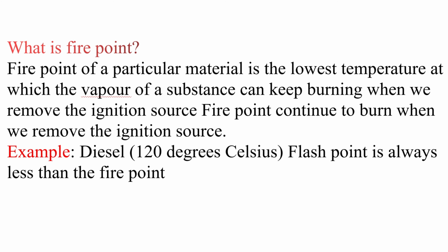What is fire point? Fire point of a particular material is the lowest temperature at which the vapor of a substance can keep burning when we remove the ignition source. Fire point: continues to burn when we remove the ignition source. Example: diesel, 120 degrees Celsius. Flash point is always less than the fire point.